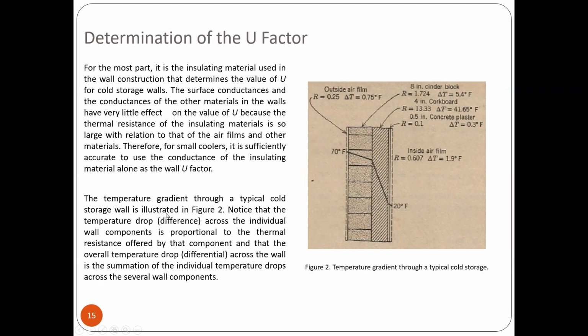The temperature gradient through a typical cold storage wall is illustrated in figure 2. Notice that the temperature drop across the individual wall component is proportional to the thermal resistance offered by that component, and that the overall temperature drop across the wall is the summation of the individual temperature drops across the several wall components. So the delta T here is 0.75. This is 5.4. So this is 41.65 to 0.3, then 1.9. So add these, subtract from that and it becomes 20. So it is not a straight line.